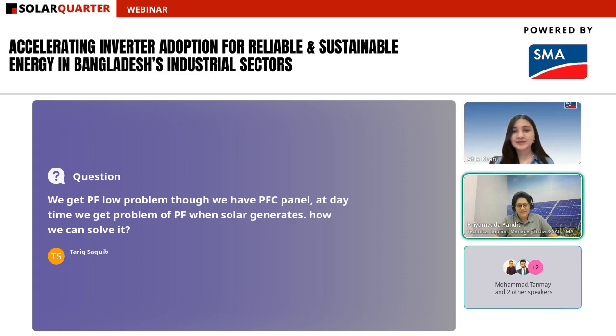If you already have the PV system installed, and if you have SMA inverters, please contact our service team - you can write to us, or to SolarHive, depending on whose contact details you have. This PF panel problem, even with a PFC panel, occurs because after including solar, the PF panel needs to be reconfigured. If that hasn't been done, it will affect your PF, because your PFC panel was originally configured for the earlier system - even if it's an APFC panel marked automatic.